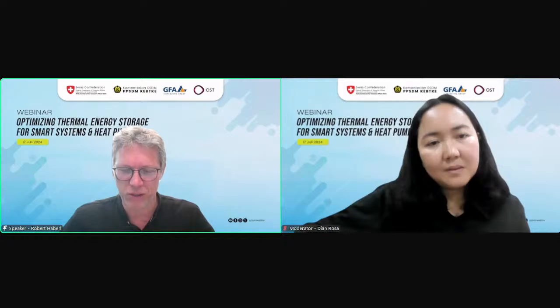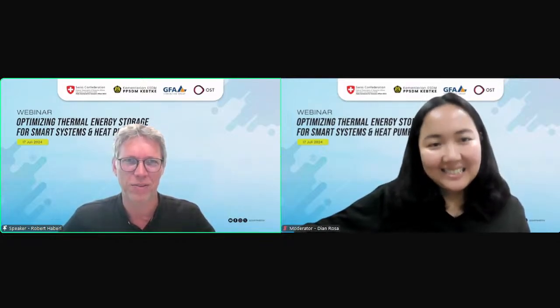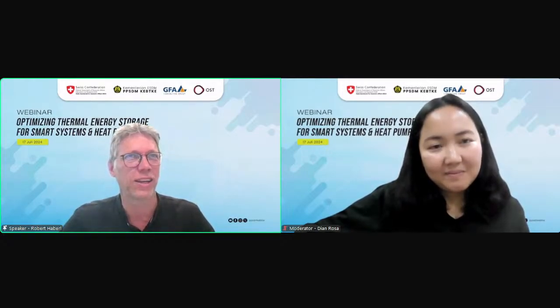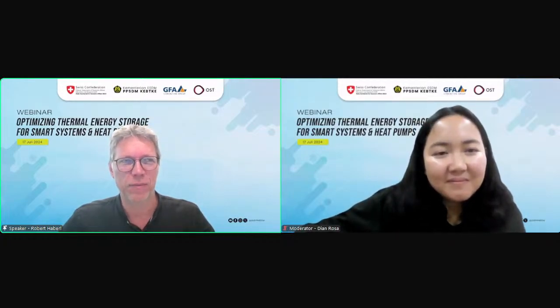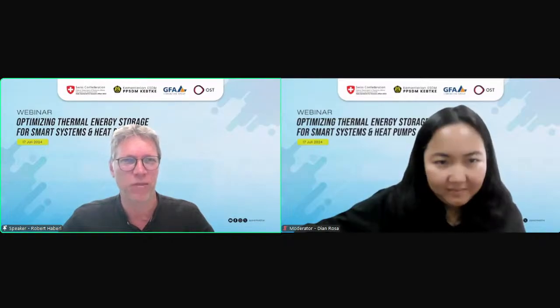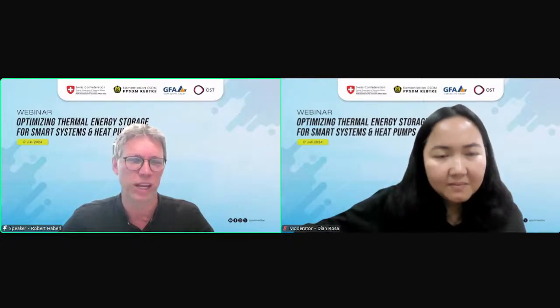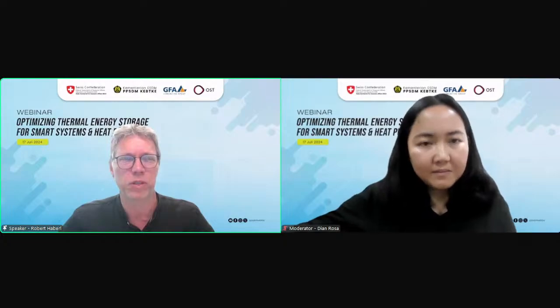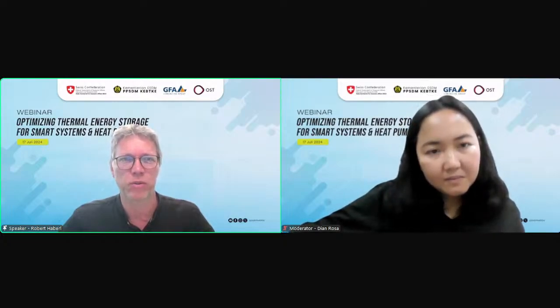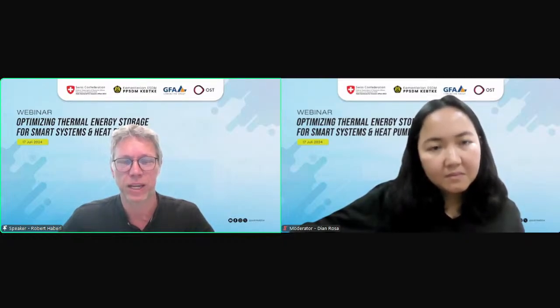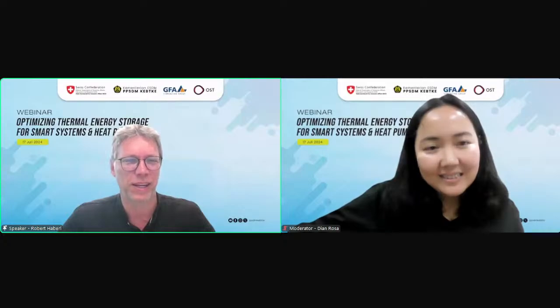The last question was about district cooling with a big storage tank. In Switzerland lately, so-called energy nets or grids are a topic, where everyone can put heat in or out, as a source for a heat pump or as a sink for cooling demands. That would mean you have the possibility to get rid of excess heat when you produce cold with a chiller, using that energy net grid. If you have a centralized cold tank to distribute the cold, why not? I think it's a nice idea. I don't see any points that speak against it.